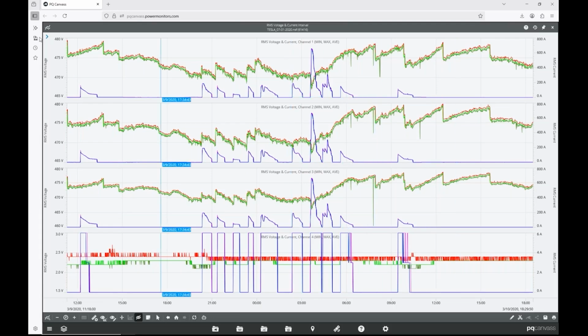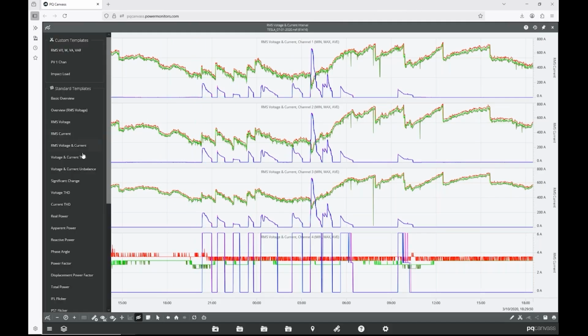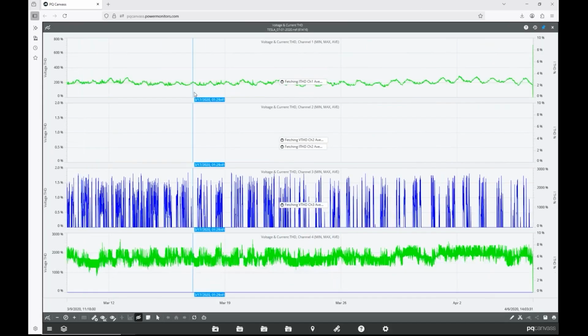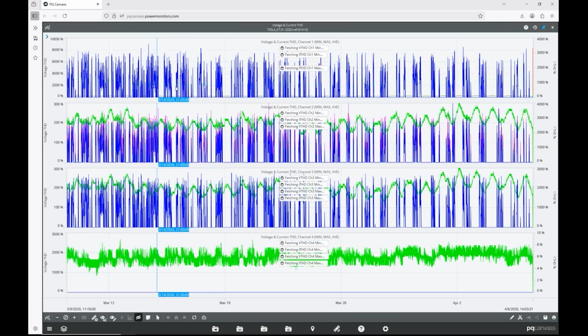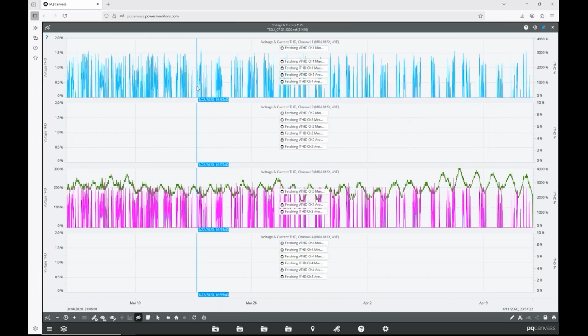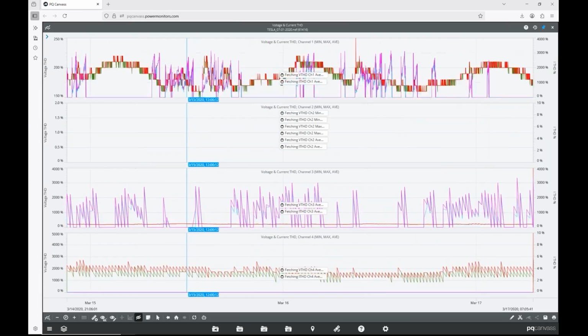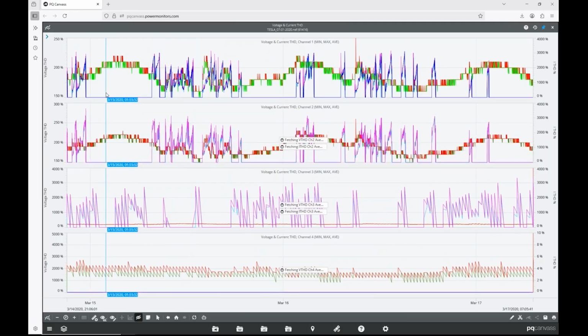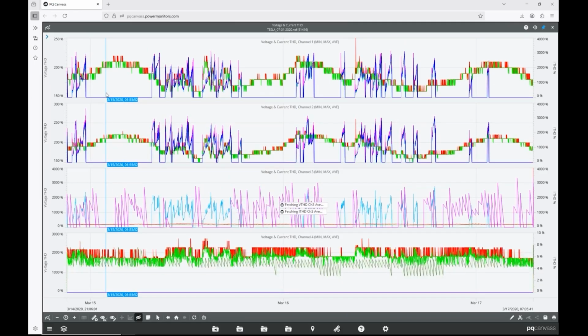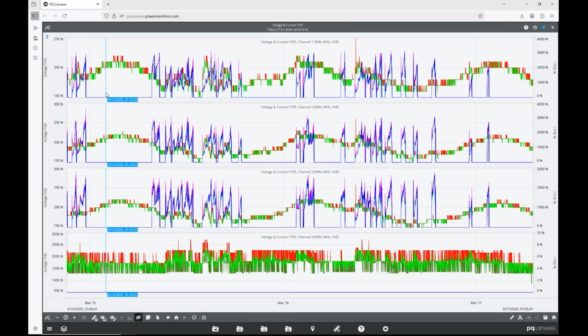Now let's take a closer look at the harmonic content. We will look at the voltage and current THD. So the green is the voltage distortion. The blue is the current distortion. And we can see that the voltage distortion is still pretty good. It's in the scaling here, it's a little bit off. It's around 2% over the whole time. So the current distortion is not pulling the voltage distortion.